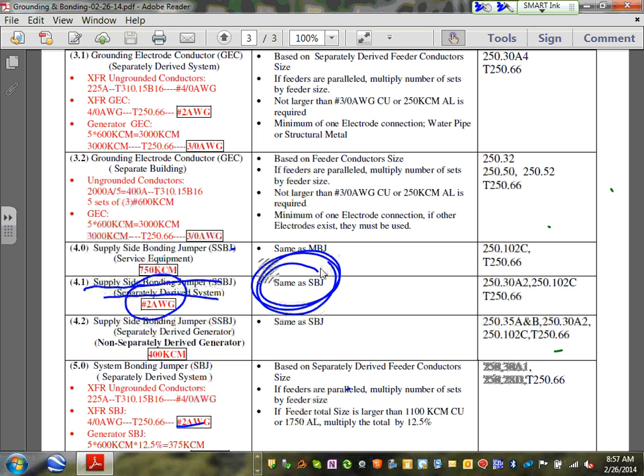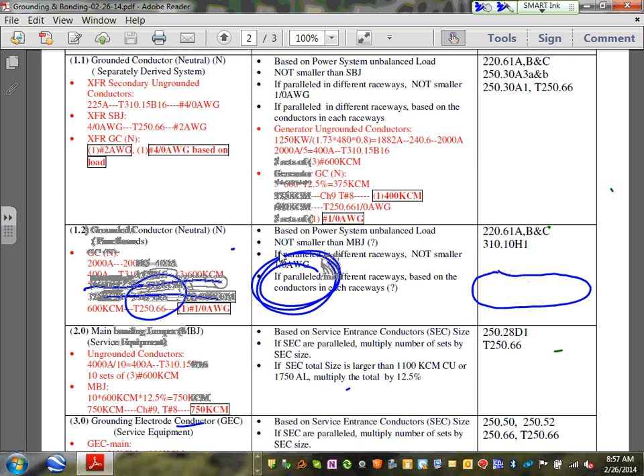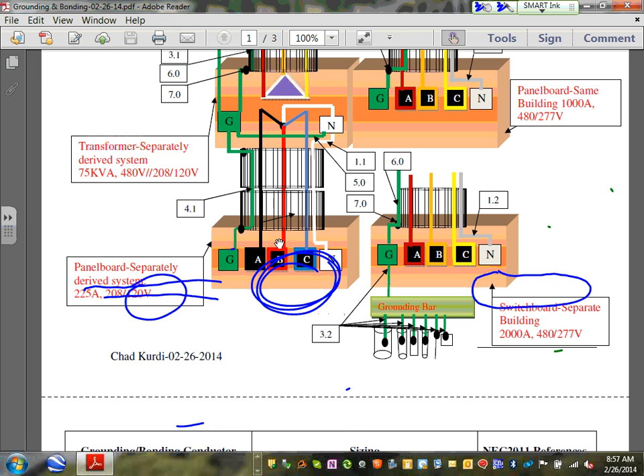If you don't believe Chad, you're going to go dig into these articles and sections, and that will tell you the same thing that I'm telling you. So the supply side bonding jumper and the system bonding jumper are identical. Okay, so that's 4.1, gentlemen. Any comments? Derek, does it make sense? 4.1, the supply side bonding jumper? Good. Okay, so I sized 1.1, 5.0, 4.1.